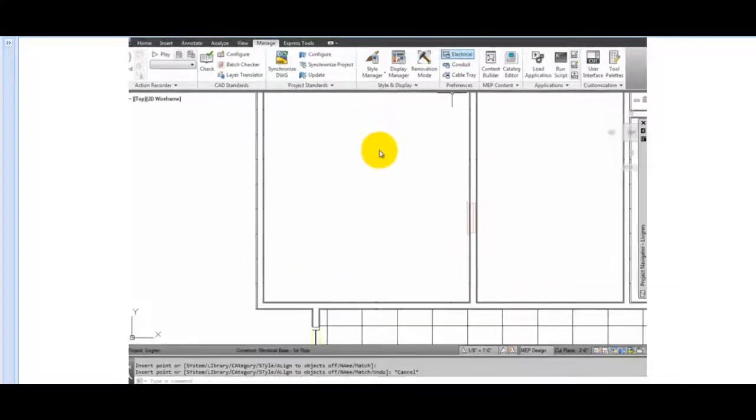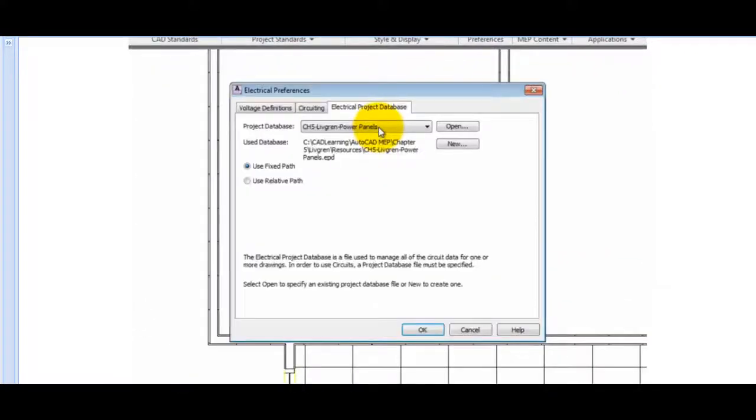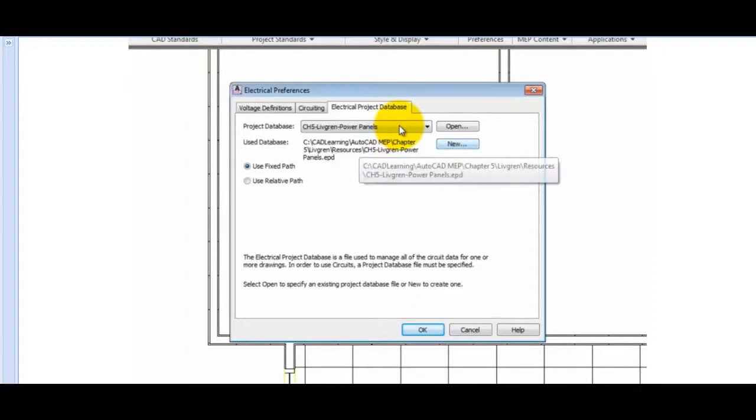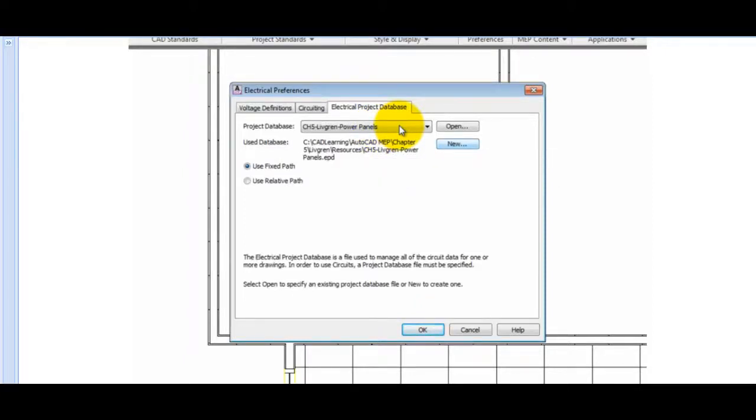A couple of rules about the EPD file. If you move the electrical project database file, use the Preferences to change the file location. Panels and devices will lose this information if the file isn't where it's supposed to be. But they will be fixed once the file is corrected.